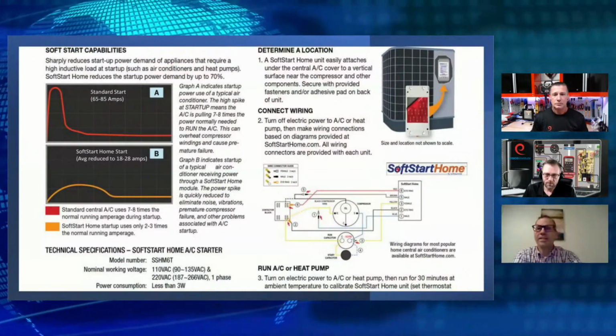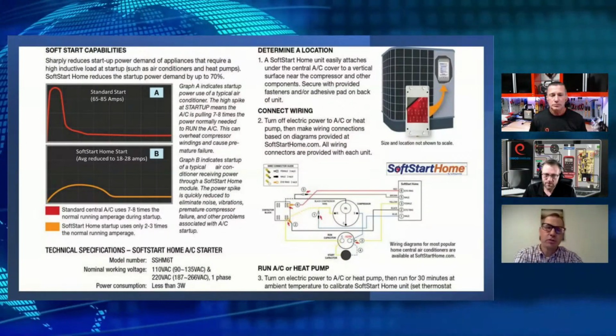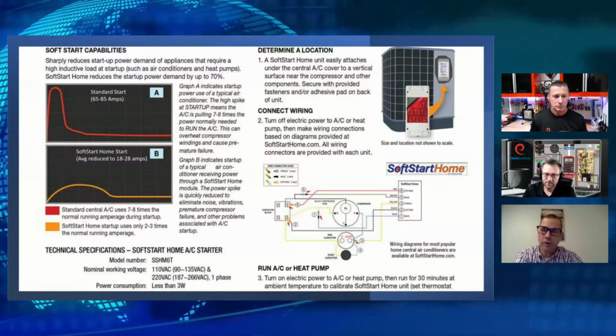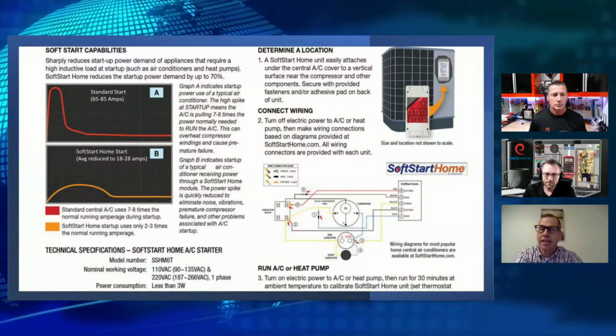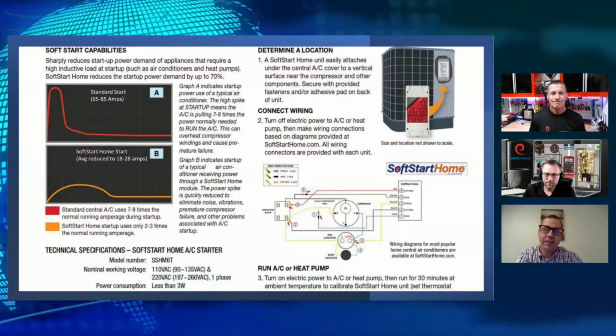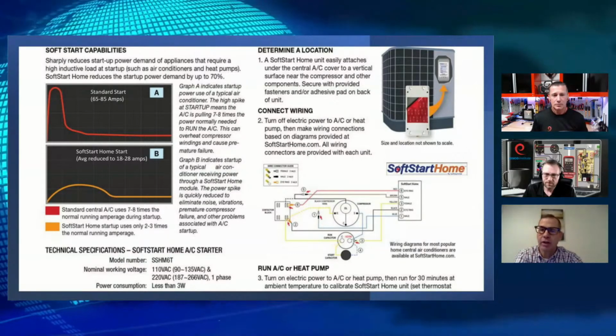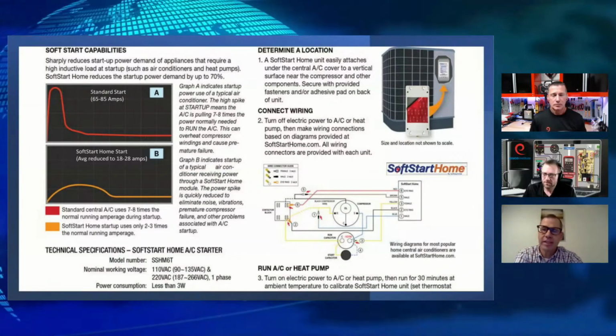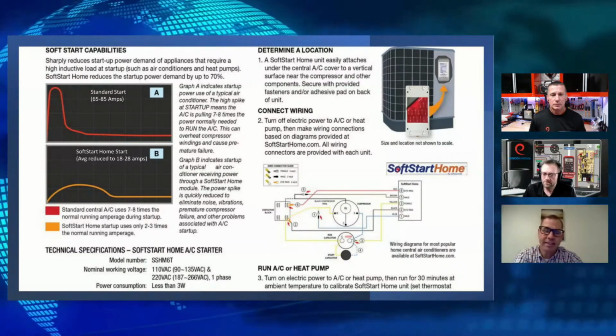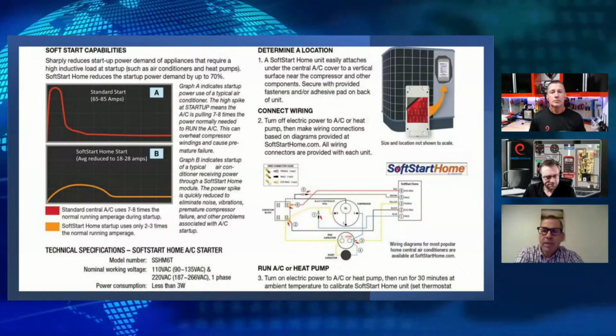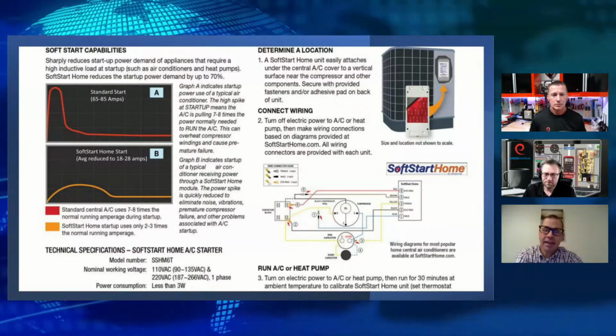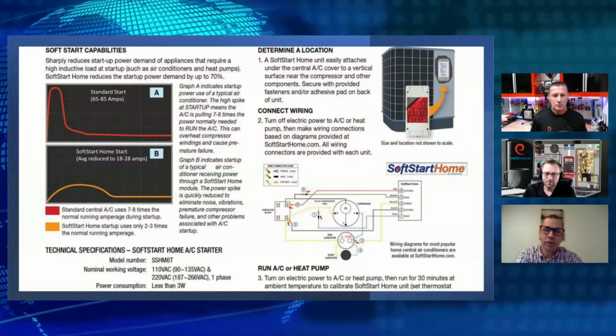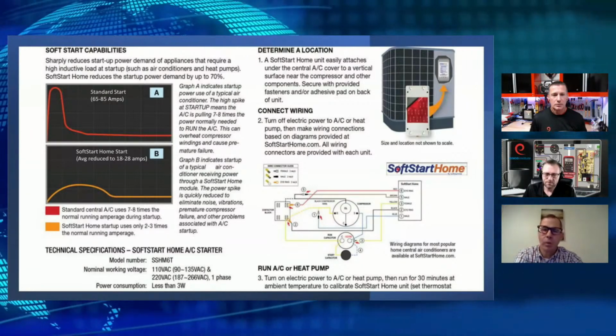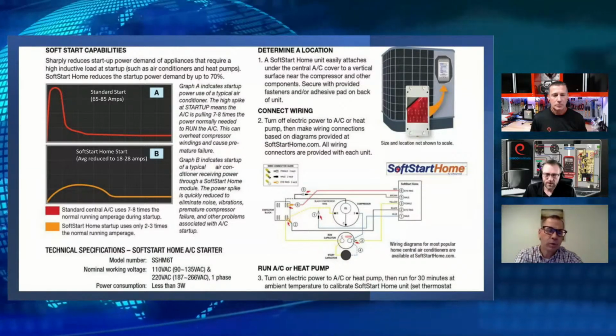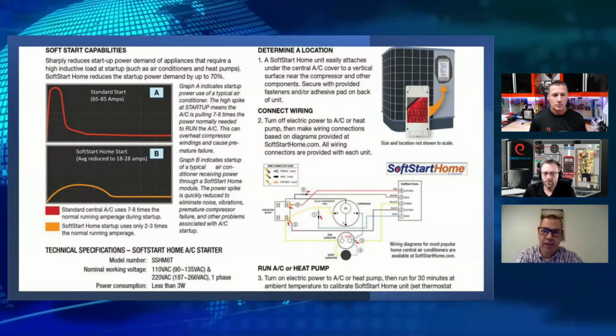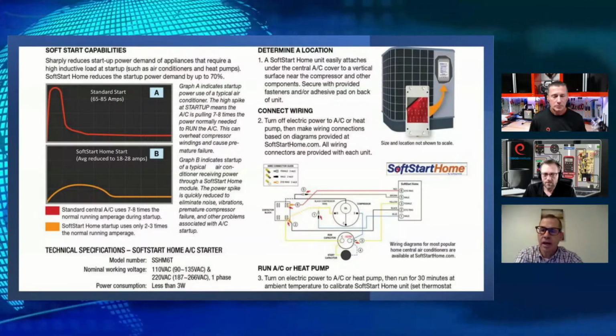This slide shows, much like your own personal experience, standard startups can be 65 to 85 amps, and after putting on the soft start, we've seen an average reduction down between 18 and 28 amps. Big difference in that inrush of amps, and what that does to the compressor over time, which can help with longevity and everything else.